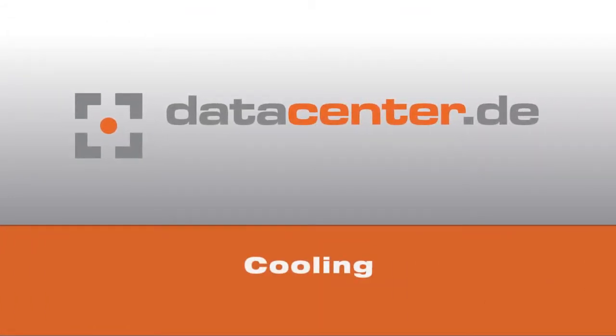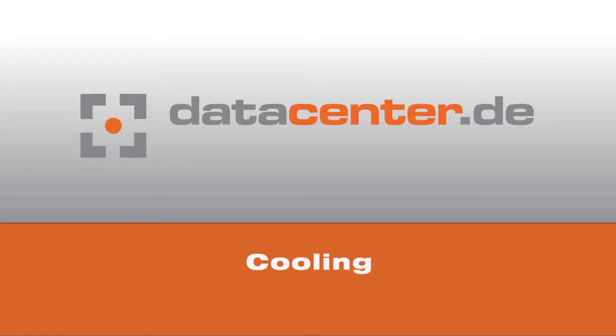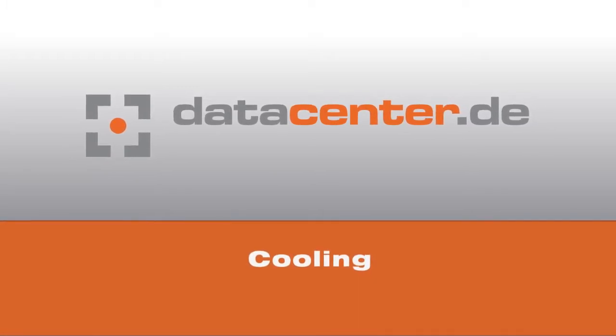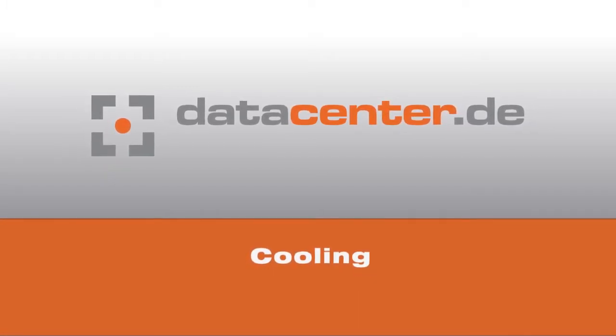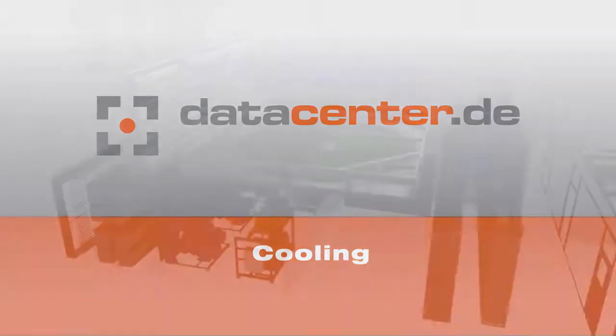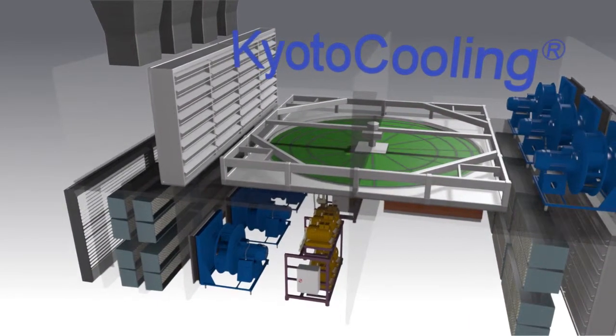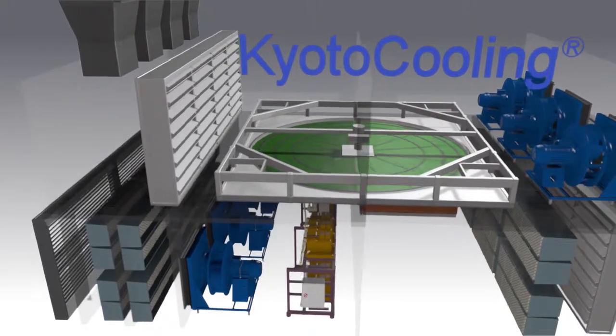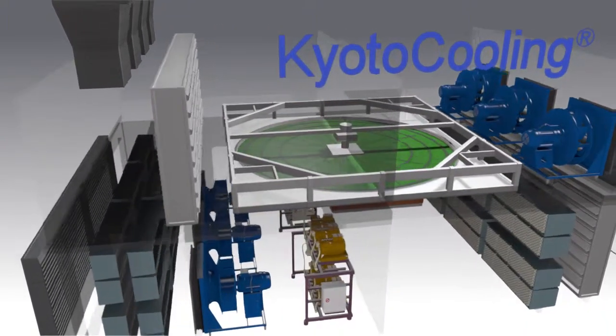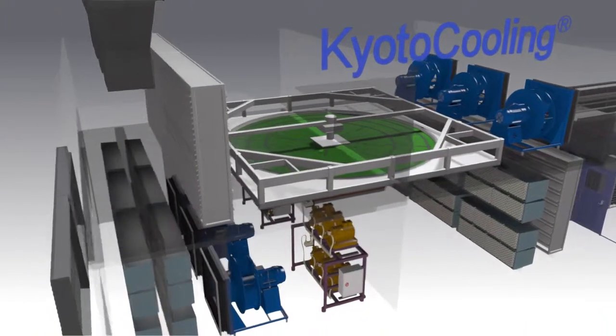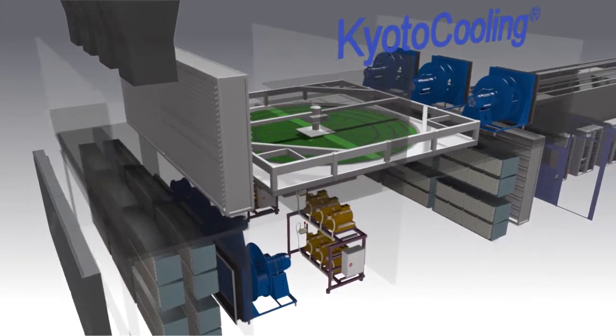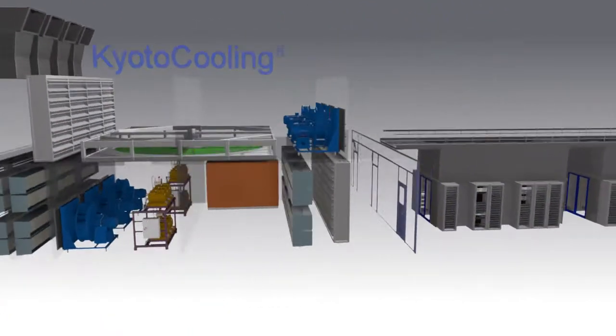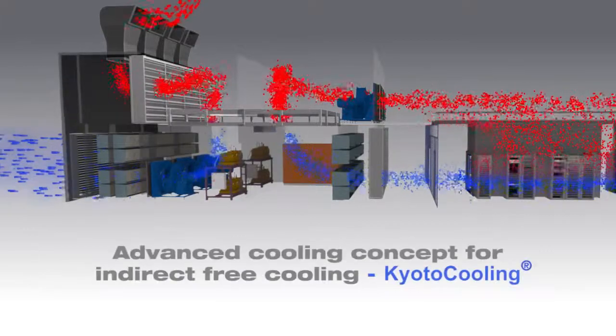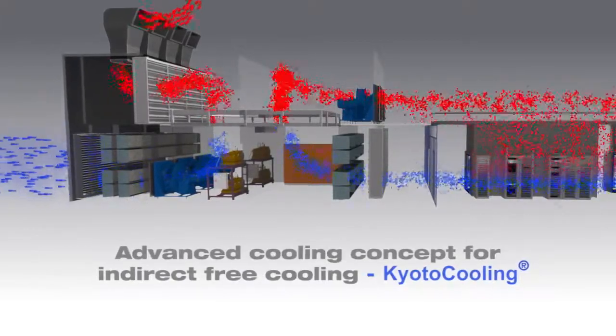Today's IT systems generate a lot of heat. More and more air is needed for cooling them, or alternatively the servers need to be spread out further, entailing additional costs in both cases. It's a different story at the data center Nürnberg 6. Thanks to the KyotoCooling system used here, the airflow can be controlled as needed via large lateral openings. Every Kyoto cell can replace any other in the event of a failure, thanks to the fully redundant design.